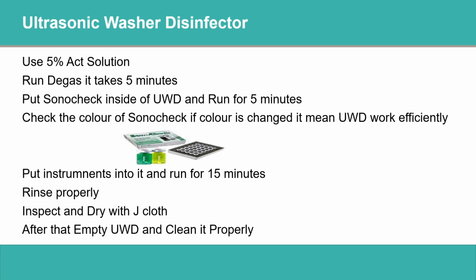Actually, in the exam they ask what the procedure is to clean this instrument, how it runs, and what the mechanism of the ultrasonic washer disinfector is. So there is a process called cavitation. What is cavitation? It produces ultrasonic waves. Because of the ultrasonic waves, it produces micro bubbles. The micro bubbles go onto the surface of the instruments, then they burst. This mechanism is called cavitation. So it uses the cavitation process to clean the instruments.